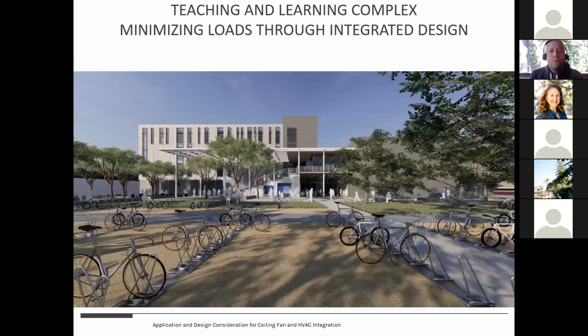One of the key elements of getting this building to work with radiant cooling was making sure we effectively reduced our solar loads. From an integrated design standpoint, we want to cut down the cooling load as much as possible. You'll notice a relatively restrained window-to-wall ratio, lots of deep shading, both for the large canopy on the south facade and in the individual classroom windows, with both vertical and horizontal shades—not all that dissimilar from your shading project.